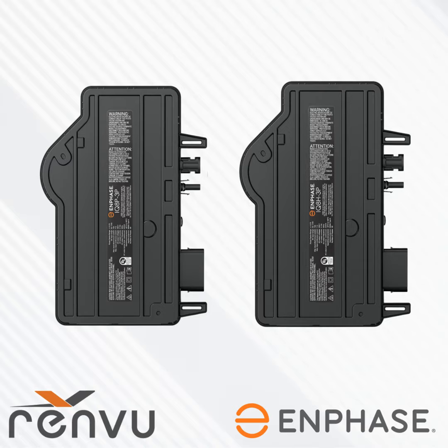All right, so again, use 208Y. If you don't have 208Y, you can get a transformer to go from 208 delta to Y, or just know that single phase is not supported at all with this product. The other thing to know is that Enphase's core competency is inverters. It is not selecting transformers. I get a lot of questions like, what transformer should I use for this, that, or the other? And it depends on a lot. I would need a lot of information to suss that out for you. So it behooves you, if you have a voltage configuration that is not 208Y, to get an EE involved to help you select the right transformer.